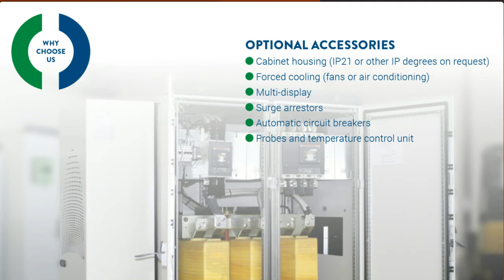To top it up, from the design of the isolation transformer itself and the manufacturing of the magnetic part, we are able to add a series of optional accessories such as specific housing, whether it is indoor or outdoor, different types of cooling systems, displays, surge arresters, or any type of breakers that is required, and temperature control and monitoring units. So in terms of what Ortea can do for data center builders as a partner is to provide a set of standard solutions which can be highly customized to project requirements or to the different installation necessities.